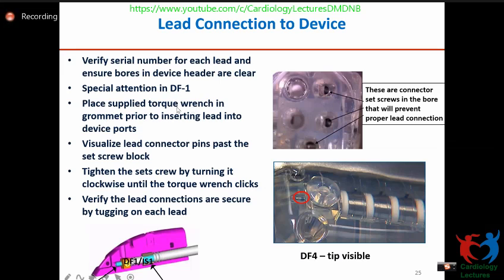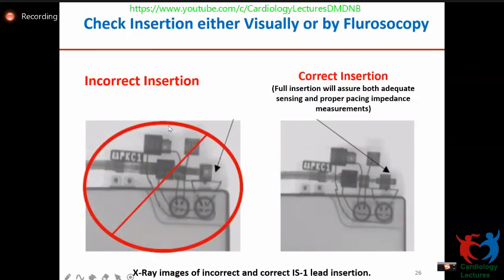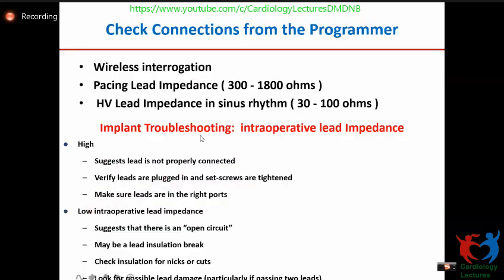Place the supplied torque wrench in the grommet prior to inserting the lead into the device ports. Visualize the lead connector pins passing the set screw block. If you're not sure, you can check the insertion under fluoroscopy to make sure the pins go through the holes.